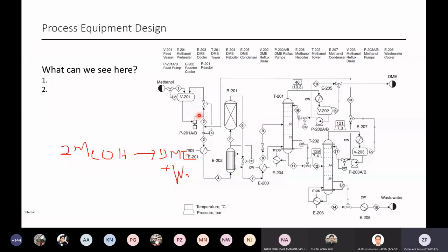So now I get the sense of how much the discharge pressure is. And then you already have the flow rate required. So it's done. Now you know how much energy you would like to get out of your pump, and then adding some efficiency loss, you get your motor power. So that's for the pump.